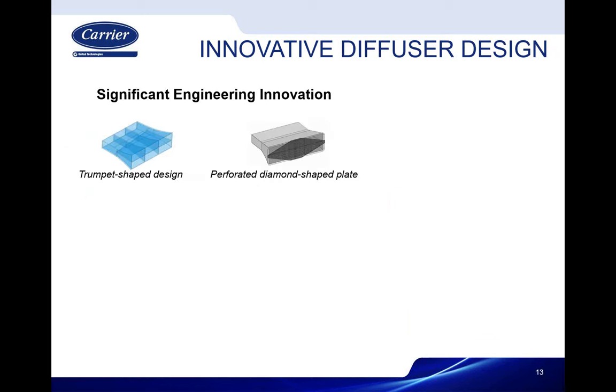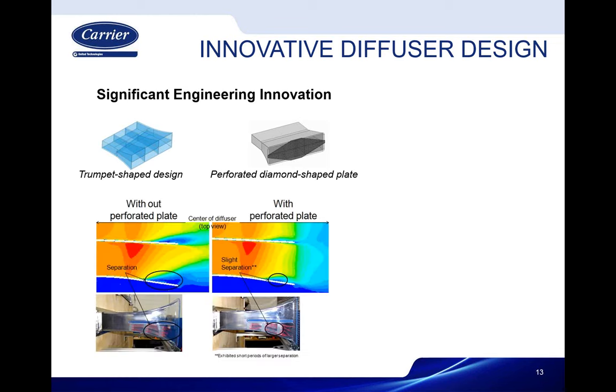The diffuser — you'll see it in one of the pictures, but essentially what was there originally was a rectangular diffuser back by the window, and we tripled the amount of air coming into the space, so somehow we had to get more area. We extended out from that window at the back of the wall, flared it like a trumpet in both directions, put a couple of dividers in to try to convince the air to stay put, use all the cross-sectional area, and get the velocities down a little bit.